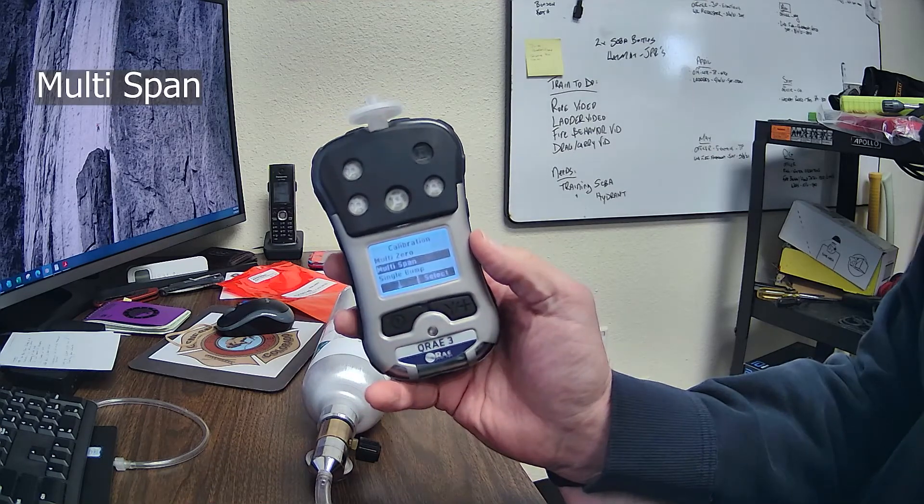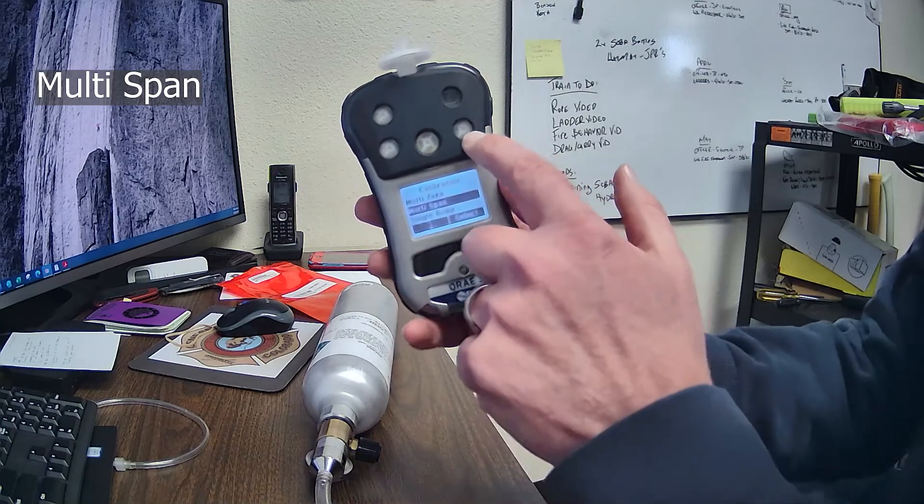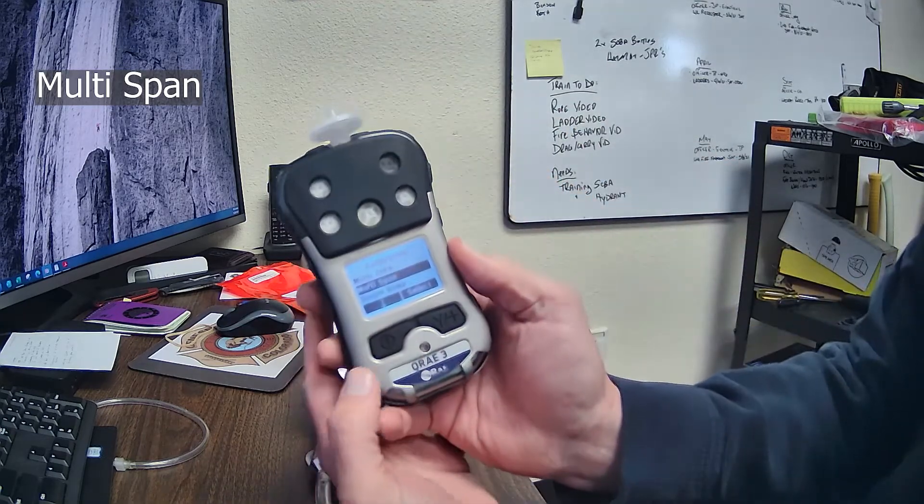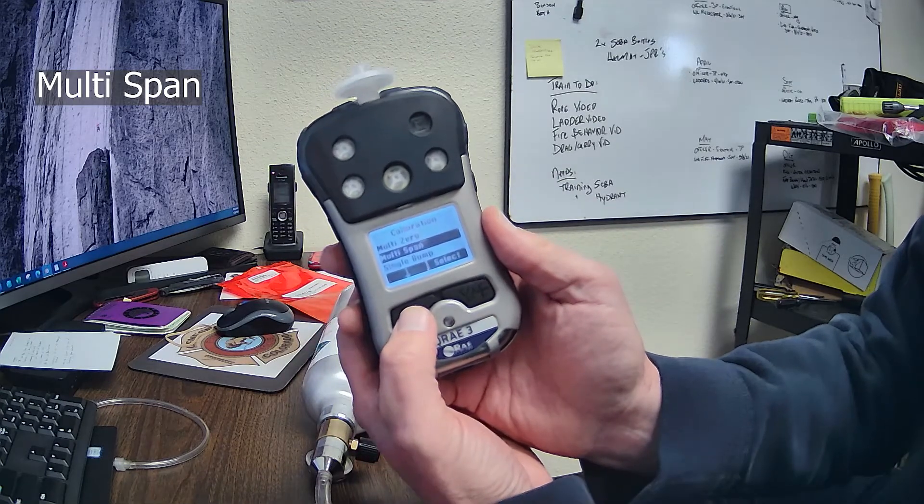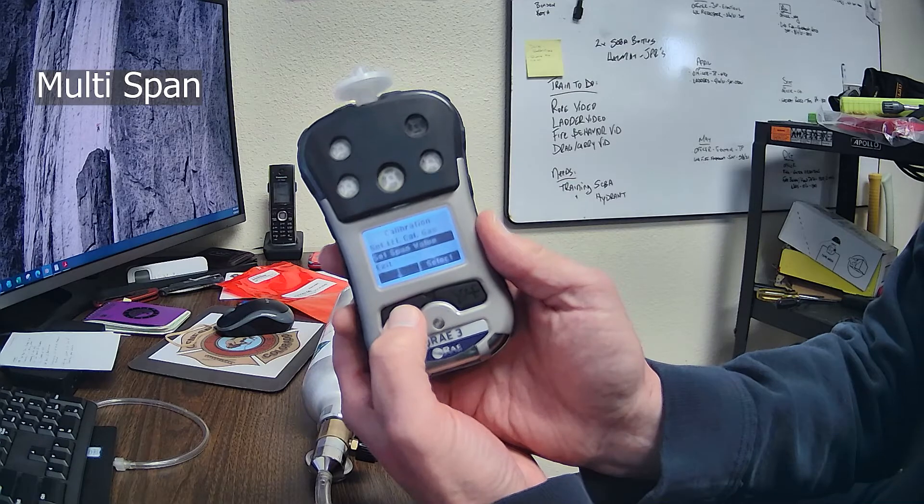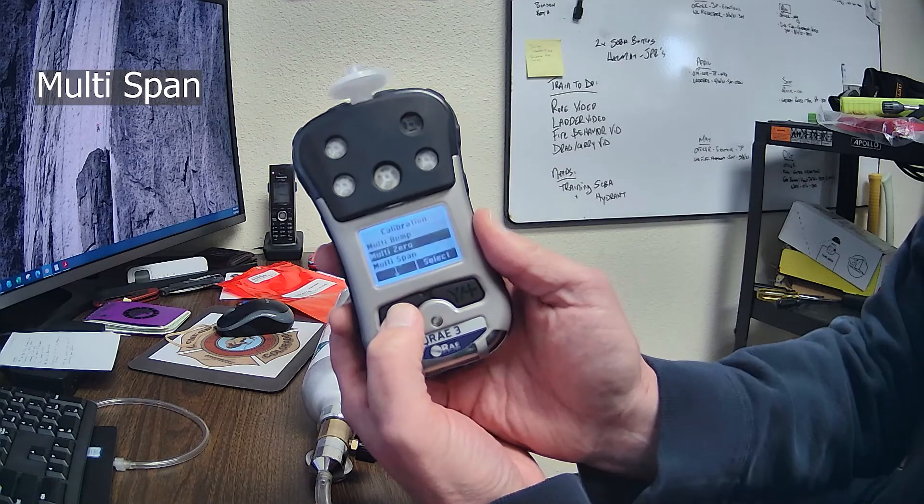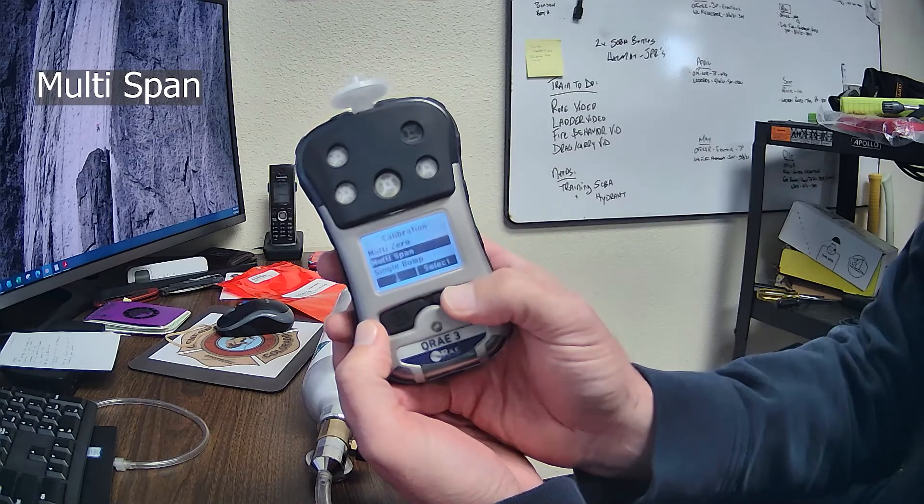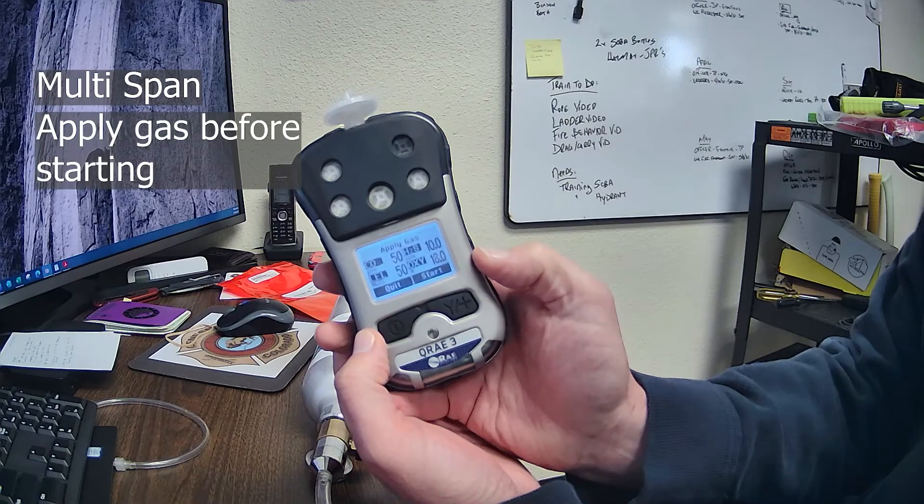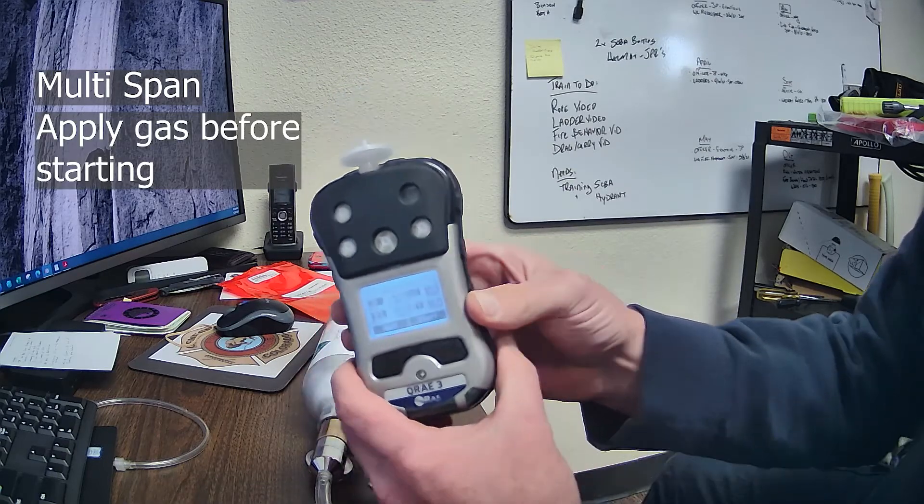We want to do the multi-span, because we have multi-sensors. All these white ones are your sensors. That one, there could be a sensor there, but we don't have it. It's empty. You could also do a single bump, single zero, single span, all these others, but we're not going to do that. We want to do the multi-span, so we're going to hit select, and say, okay, apply the gas.